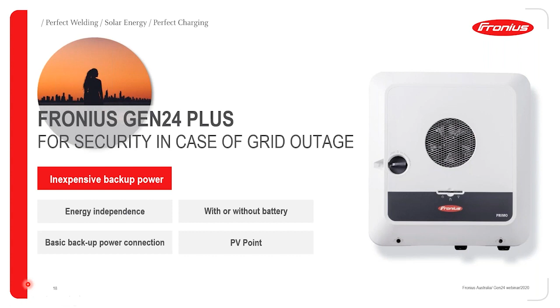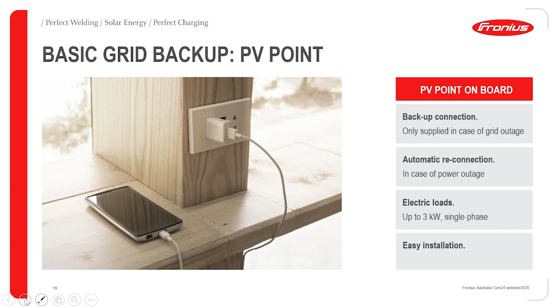The PV point is basically a GPO, which looks like that, and this GPO is wired to the inverter. On the inverter, there's a special dedicated AC output that goes to this part - an automatic reconnection if the grid goes down. The maximum load from this port is 3 kilowatts, single phase only, and it's an easy installation.